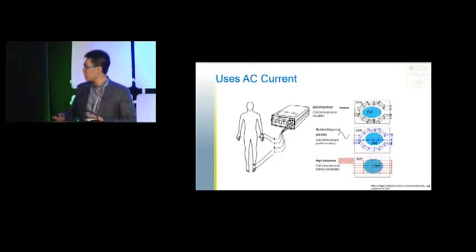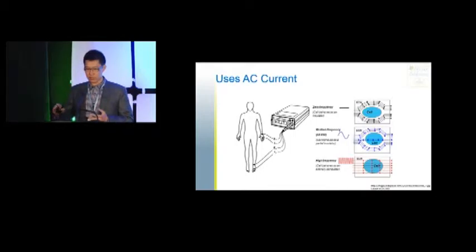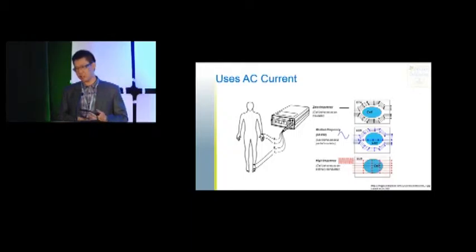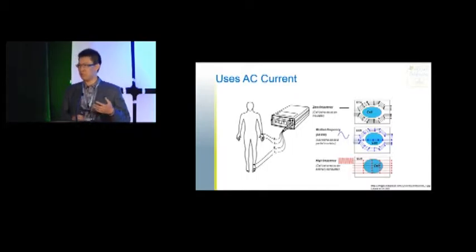How does it work? You can see a diagram of a person on the left-hand side, with the machine represented as a box, and two connectors to the upper limb and two to the lower limb. Different currents are applied — at no frequency, all the current passes through extracellular water. As the frequency is applied at various levels, it passes through part of the cell. By subtracting the measurements, the machine is able to calculate what the composition of the cells are, as different frequencies show different things.